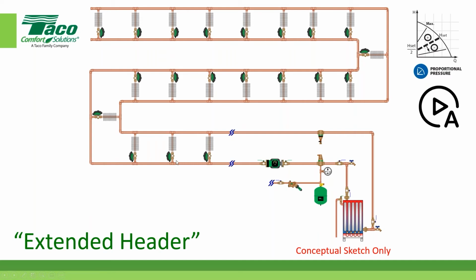Now, is that slowing down of the pump going to create more or less flow in the header? Of course, it's going to create less flow in the header. When we create less flow in the header, is that going to be more or less resistance that the pump is going to see? Well, of course, it's going to be less. And guess what? That's why this pitch up here works good for these types of piping where you have an extended header, because as the zones close, there's a reduction of flow. A reduction of flow is a reduction in pressure drop, and the pump knows that and can feel that and gradually works its way down to a lower RPM. So hopefully that helped explain that.